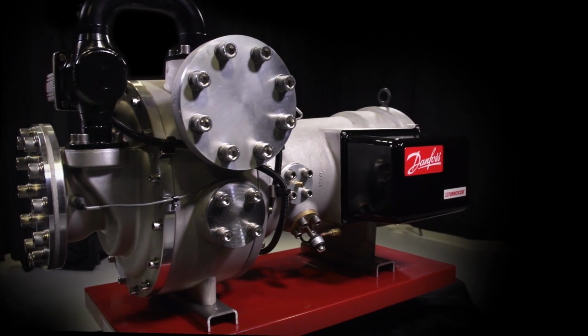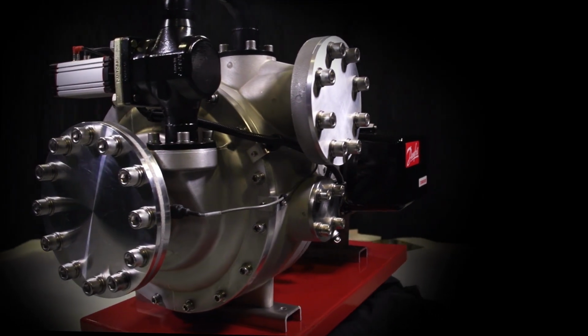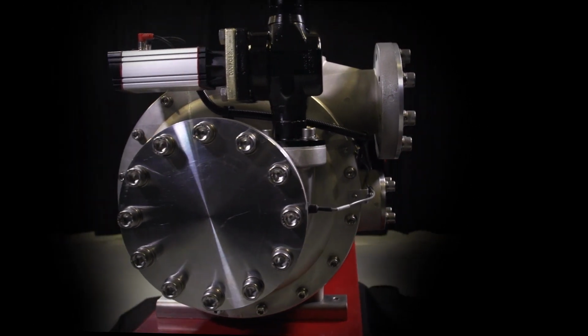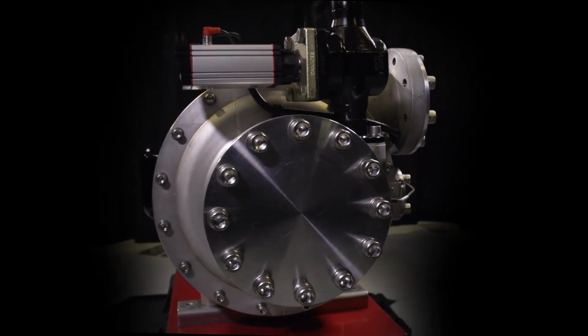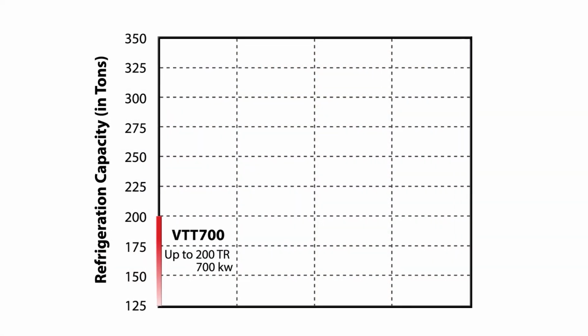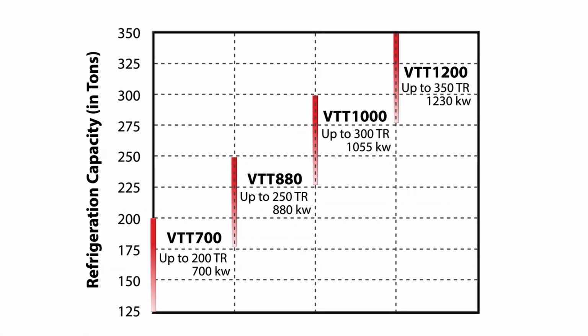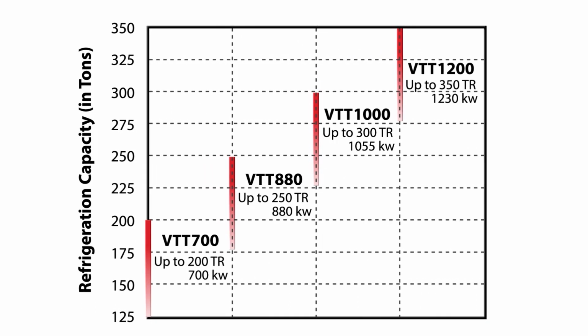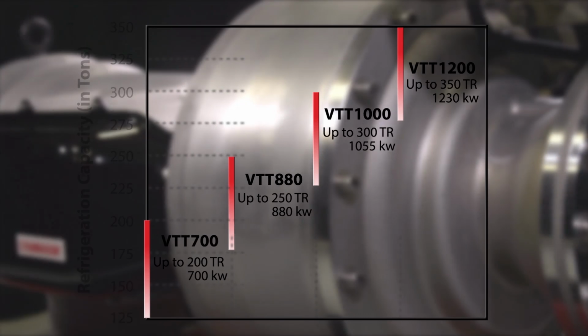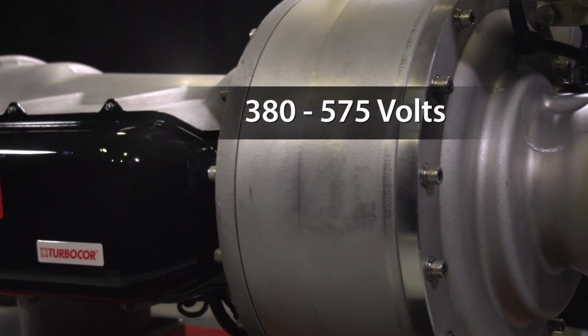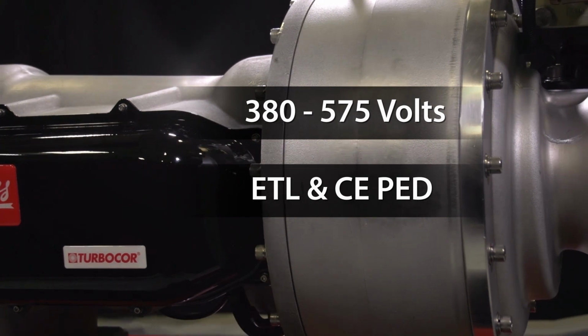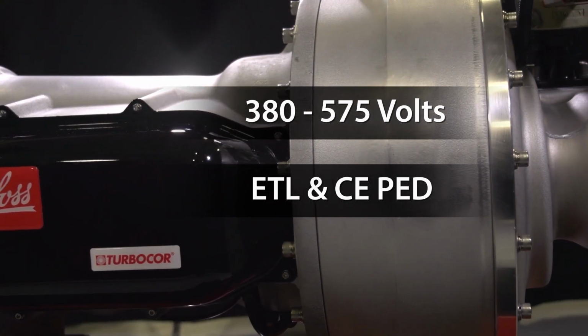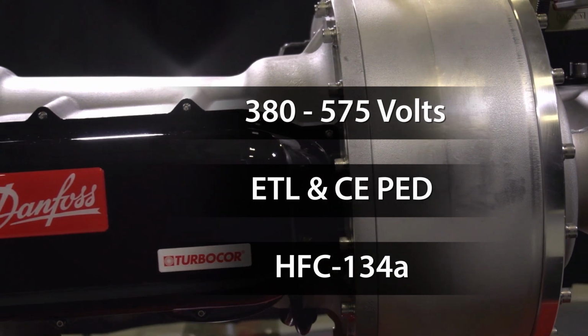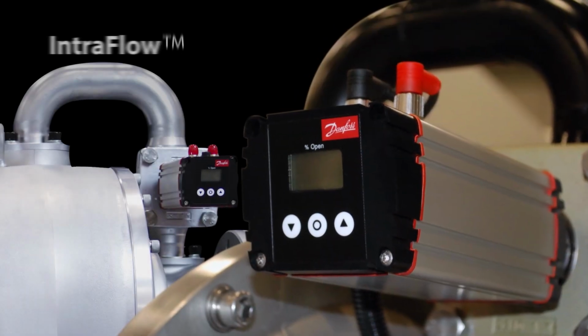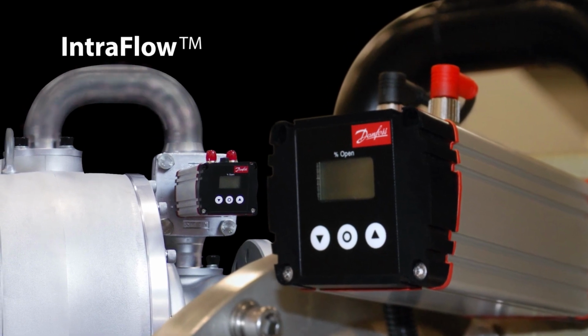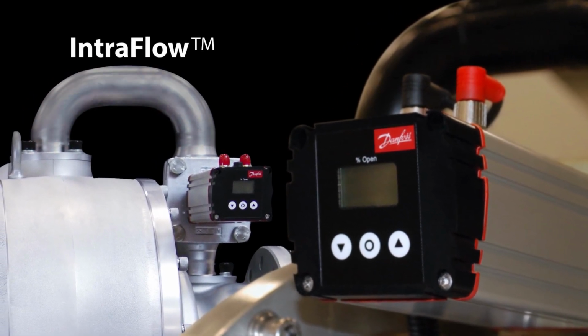The VTT delivers expanded capabilities and superior performance. Besides the benefits that come along with the variable-speed, oil-free technology that Danfoss Turbocor is known for, the VTT series of compressors also provides best-in-class full and part load efficiency. With capacity breakpoints of 200, 250, 300, and 350 tons, a combination of drive and compressor modules form the VTT compressor. Designed for voltage applications between 380 and 575 volts, the VTT series includes ETL and CE PED certified models and uses HFC-134a refrigerant. Using a patented technology called Intraflow, these compressors are intended for chiller applications with water-cooled systems up to 1,000 tons and higher.